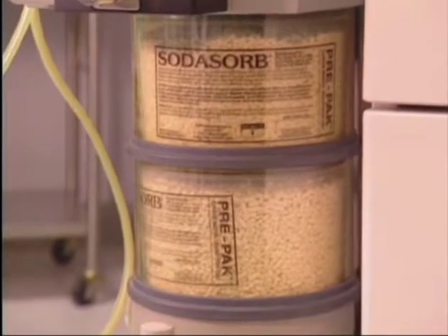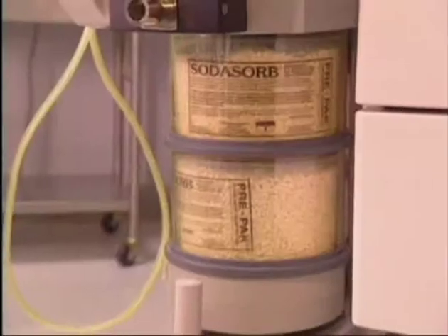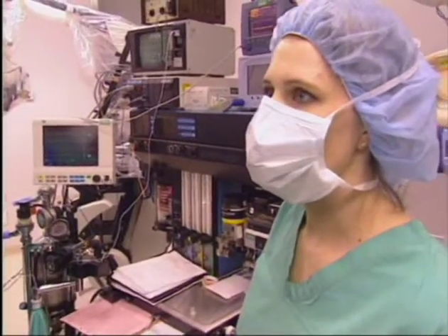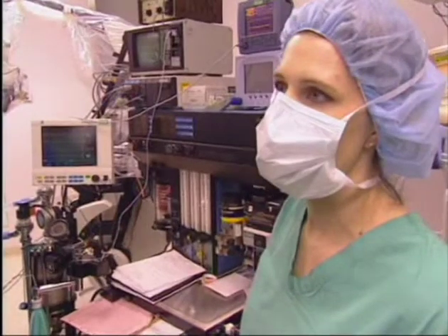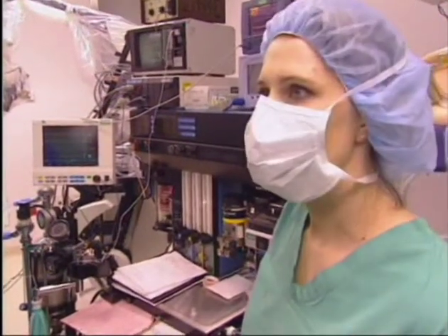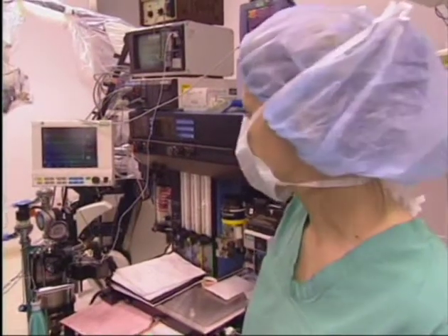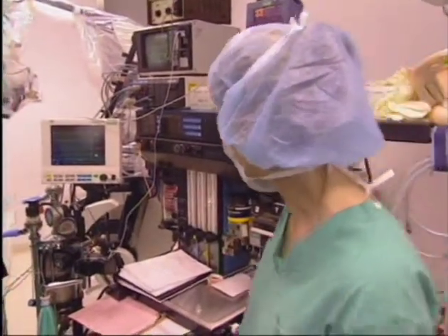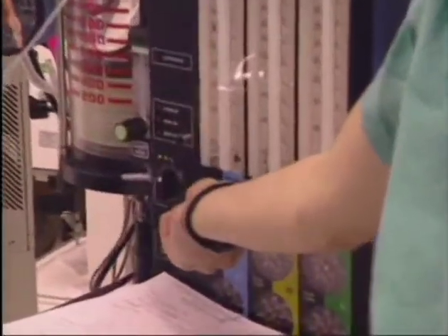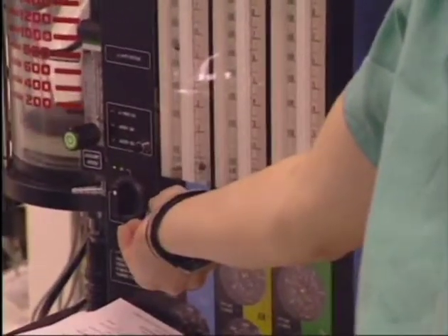And what does that do to the carbon dioxide that gets to the absorbent? Basically, it's decreasing the amount of carbon dioxide that actually gets to the absorbent, which helps. And a decreased amount of carbon dioxide decreases the temperature of the absorbent, which also decreases compound A production. So the temperature just doesn't get very high in the absorbent at this flow rate. Right. All right, now let's go down to a lower flow rate. Let's go down to 500 cc's of nitrous oxide and 500 cc's of oxygen.